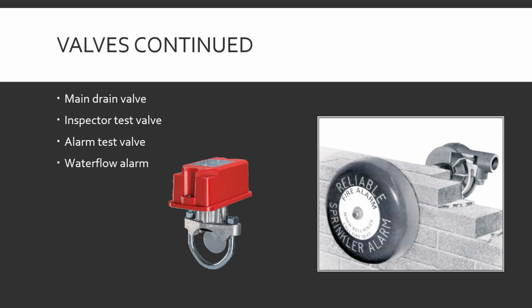Main drain valve. Lowest point in the system. That's for when they have to do major work on the system. The fire alarm system, the sprinkler company comes in, shuts the water off, opens the main drain, empties all the water out of the system.